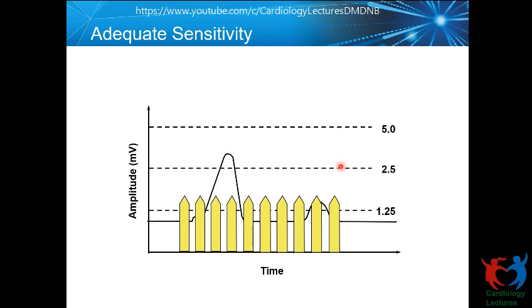So typically the pacemaker ventricular sensitivity is 2.5 or 2.8 millivolts. And that is why we want to get an R wave of 5 millivolts, which means I want to have a two-fold safety margin. The R wave amplitude may change for any patient for various reasons to some extent.